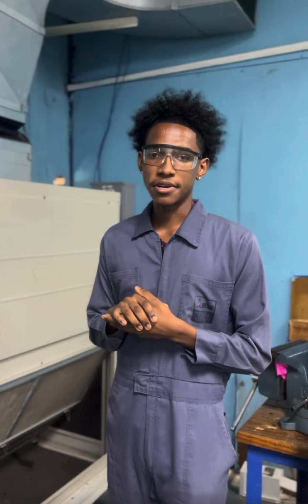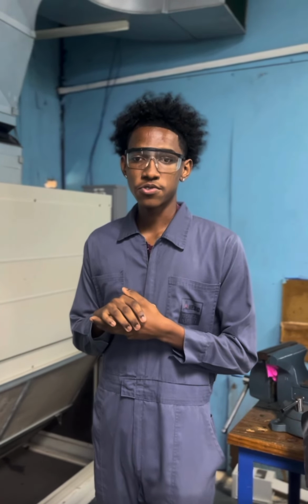Flow hoods are devices designed to control and measure airflow by maintaining clean, controlled air movement. In HVAC applications, a flow hood, also called a capture hood, is a portable instrument used to measure airflow from supply diffusers and return grilles during system balancing and commissioning. In clean environments, flow hoods may also use HEPA or ULPA filtration to provide contaminant-free airflow that protects sensitive products and processes. Flow hoods are essential tools for accurate airflow measurement and for maintaining safe, controlled air conditions during HVAC balancing and specialized clean air operations.